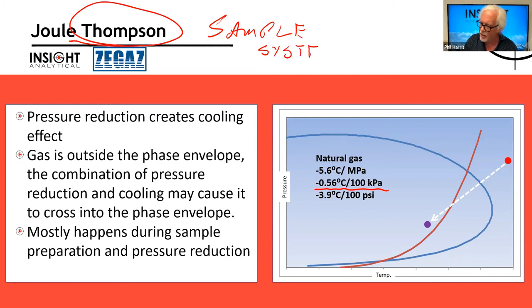So this is a common problem a lot of times in our sample systems. If we're using an analyzer that's going to run at ambient temperatures and ambient pressures, like a tunable diode laser system for moisture analysis, you have to drop the pressure before you get into the analyzer. They run at around 1 bar. Pipeline pressure is around 60 bar. So if I drop 60 bar, or 60 atmospheres, I'm going to drop the temperature by 30 degrees C. So even if my pipeline gas isn't at its dew point, when it goes across that regulator, I run the risk of hitting condensation.